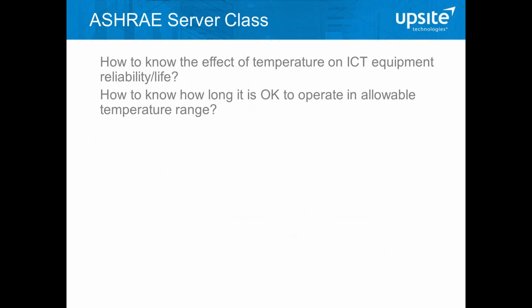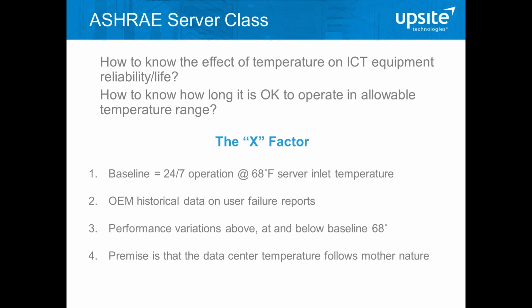Now, one thing we need to ask ourselves while we're considering these server classes in these temperatures that may allow us to run our data center occasionally up into the 90-degree range or higher, is what is that going to mean for the reliability of our computing equipment, and how long can we actually allow ourselves to wander into some of those higher temperatures and still meet our reliability and availability goals? Well, the answer to those questions come with the ASHRAE process, which they define as the X factor.